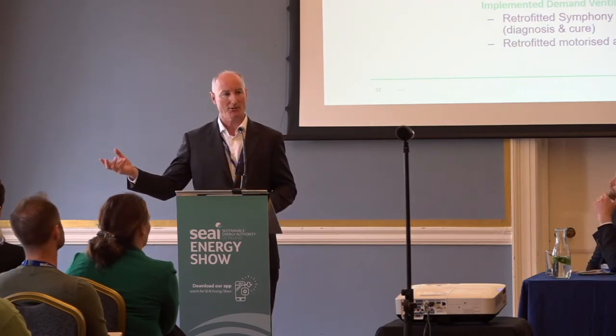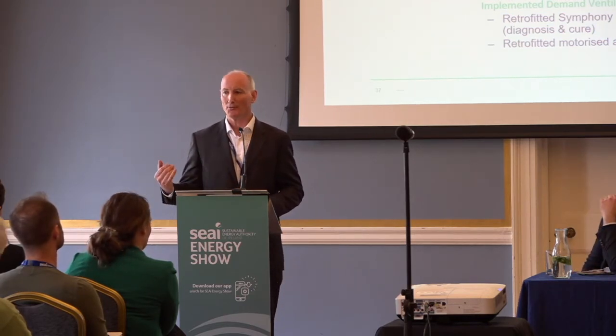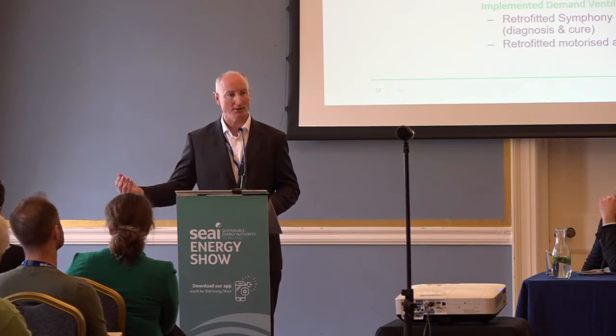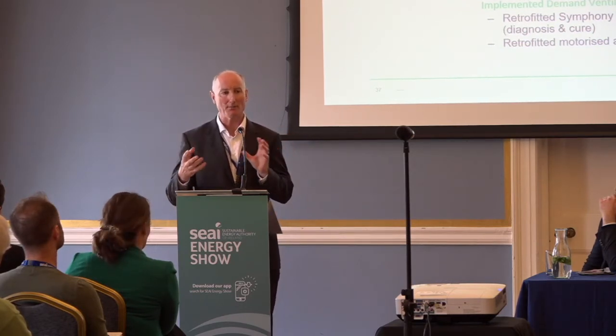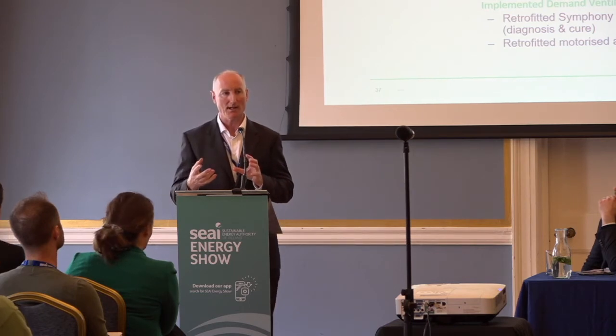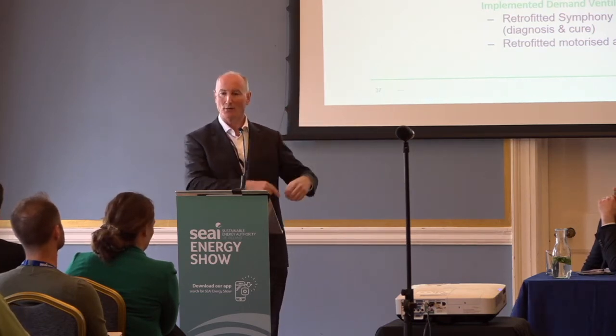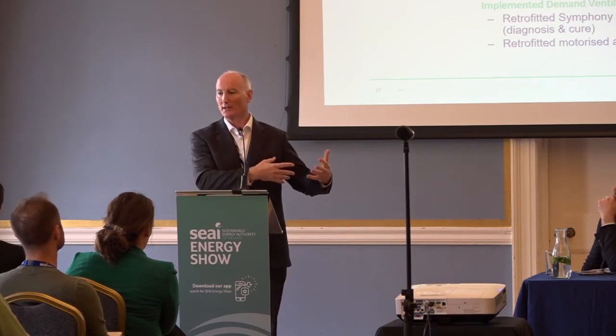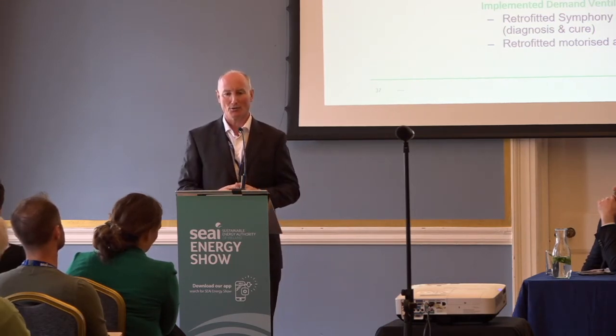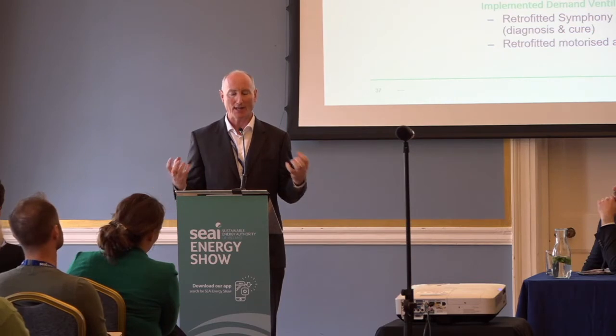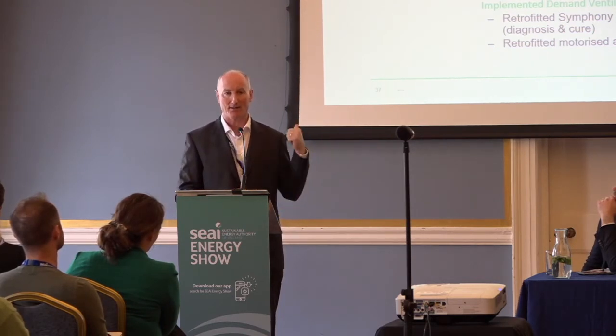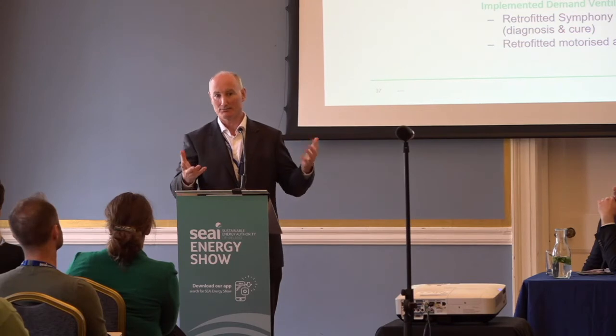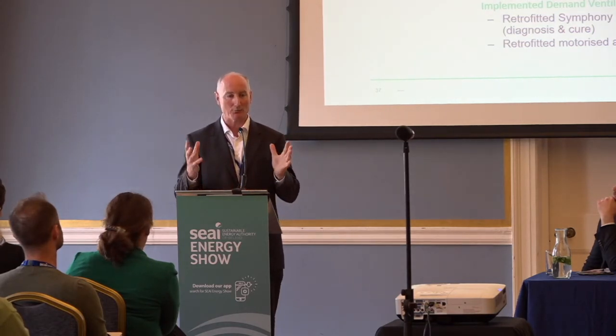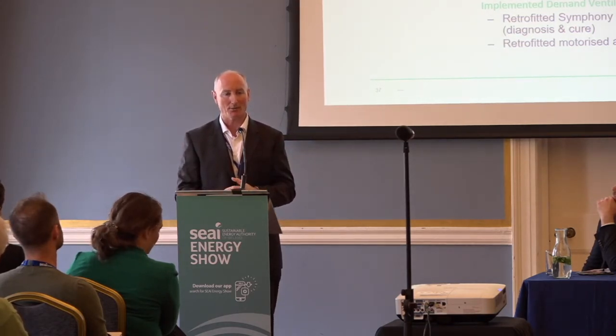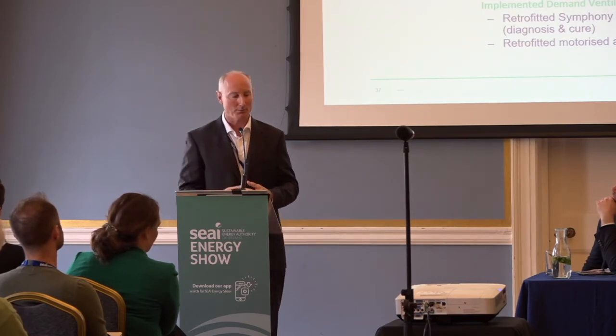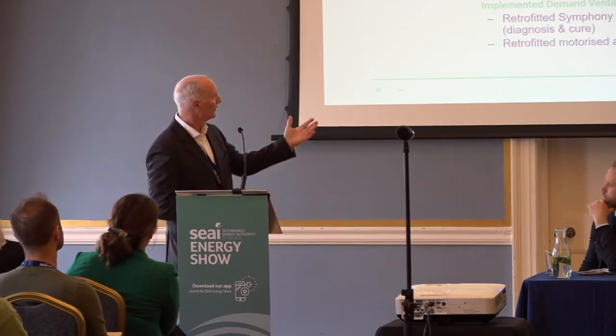On the other hand, the heating system has been able to back off much earlier. I'm seeing the heating system knock off at 6 to 8 degrees outside, because the remaining heat needed in an efficient building is just top-up heat on the air supply. We're offloading that as waste heat gathered from hotspots in the building. So we're seeing free heating and free cooling. It's absolutely phenomenal — the impact this has for climate objectives across the world is phenomenal, and it's a very straightforward process to implement. So we have that in place: free chilled water and free heat.